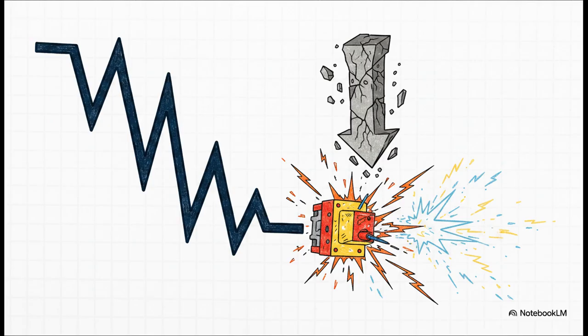In a low-inertia grid, the rate of change of frequency, engineers call this RoCoF, gets dangerously fast. Our safety stability margins shrink way down. The overall system strength, which is measured as short-circuit ratio, drops drastically, meaning the grid's voltage gets incredibly twitchy and sensitive. And worst of all, protective relays can get confused by the lack of traditional fault currents. They might start tripping unnecessarily, disconnecting even more power, and suddenly you're looking at a cascading blackout.